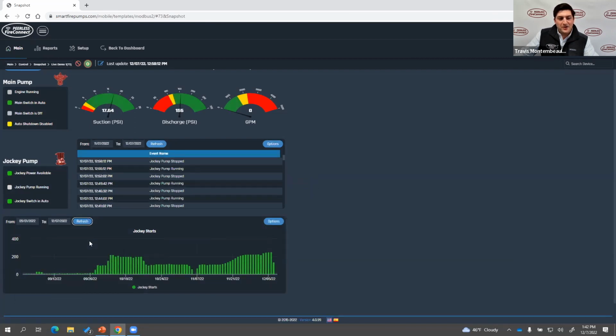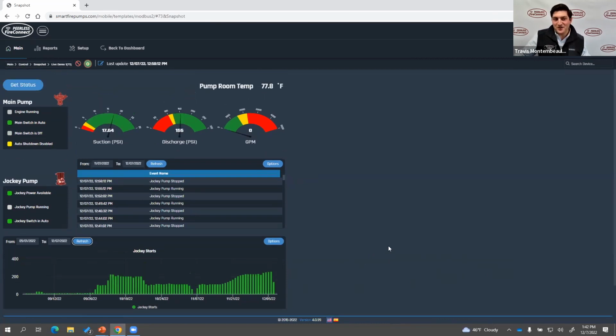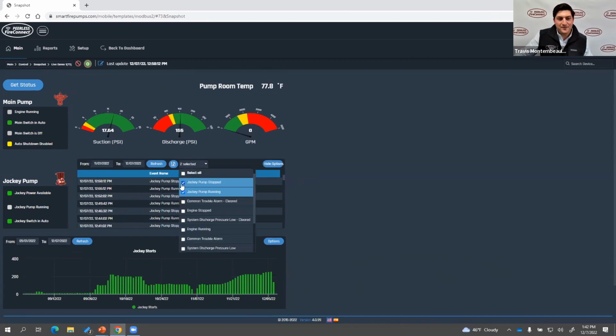And if you zoom out a little bit over time, you can see different performance of that jockey pump. So we're talking about looking at system health, for example. This is a really good indicator on the snapshot page of what's going on. Back to this event log, I opened the filter a little bit so we can see what other alarms we've received, for example, or what other conditions we've received.